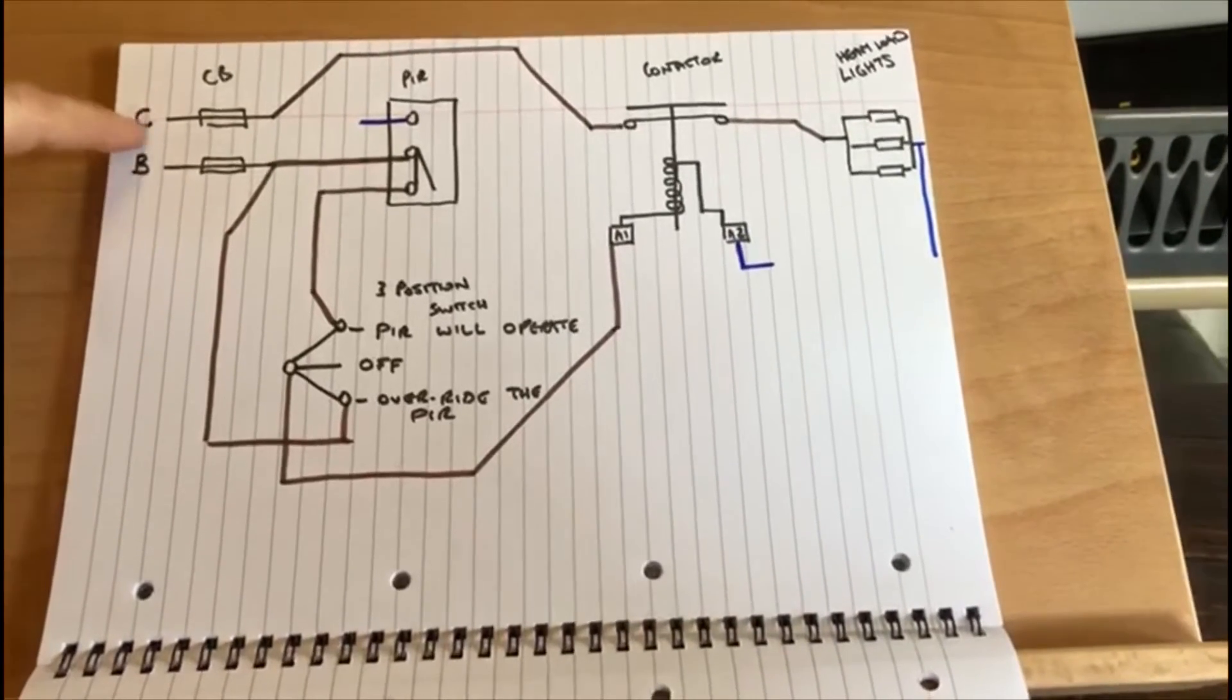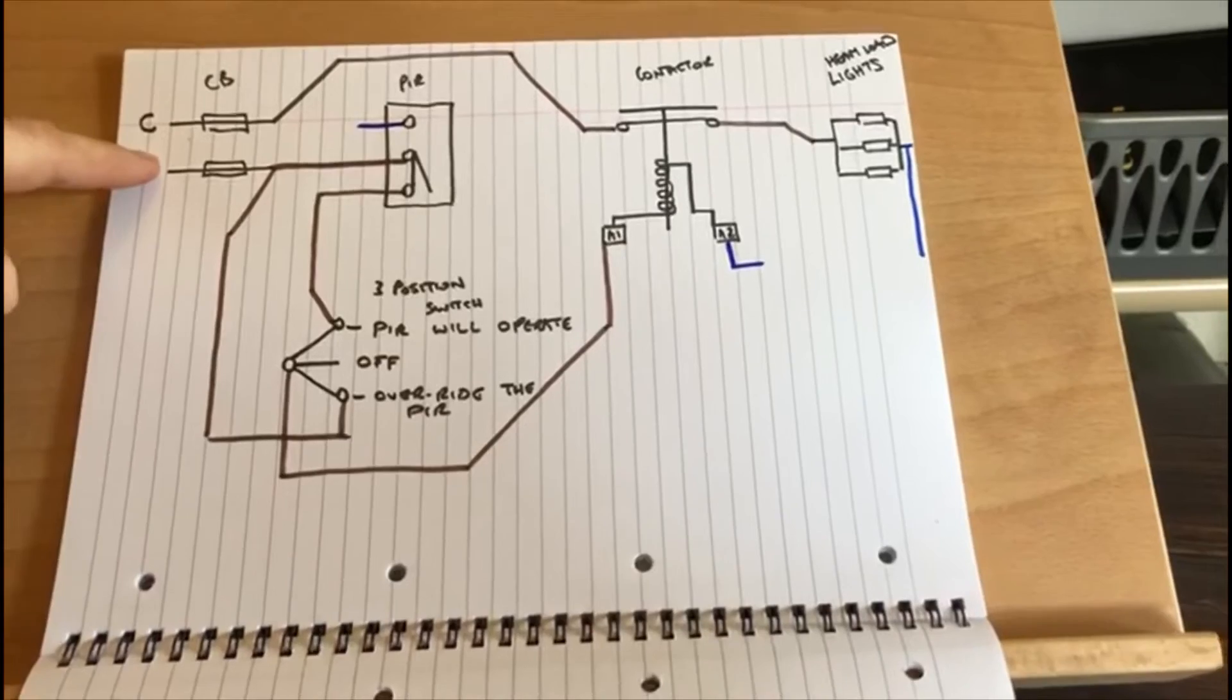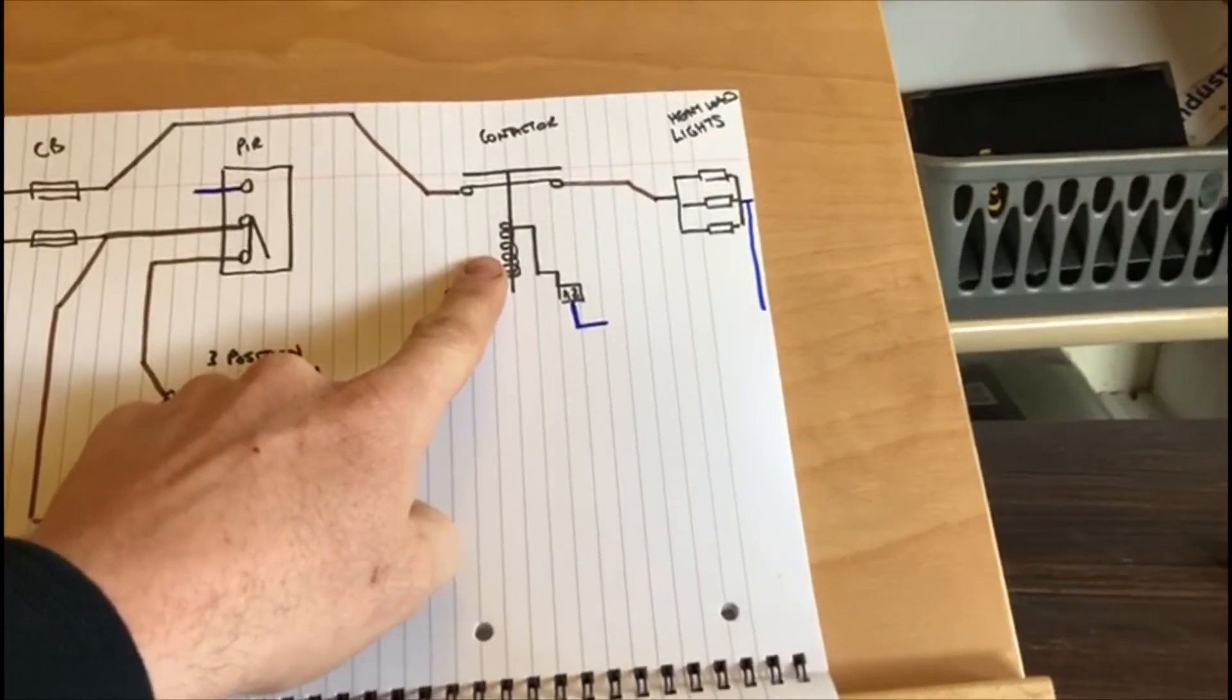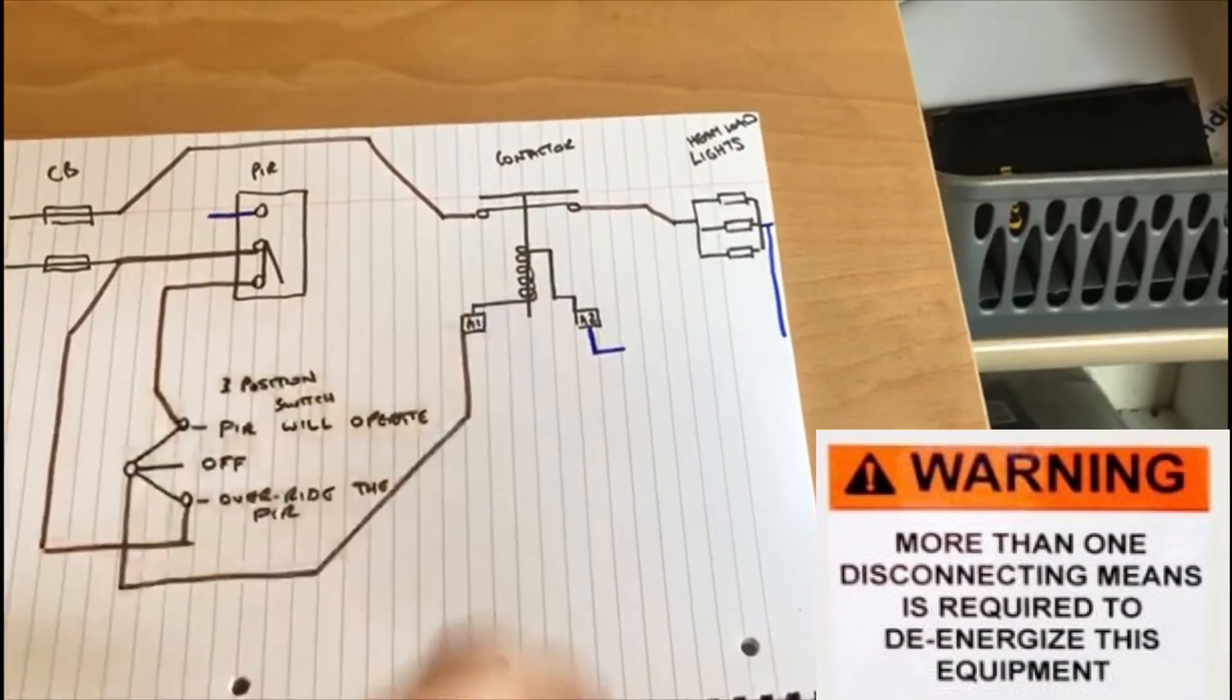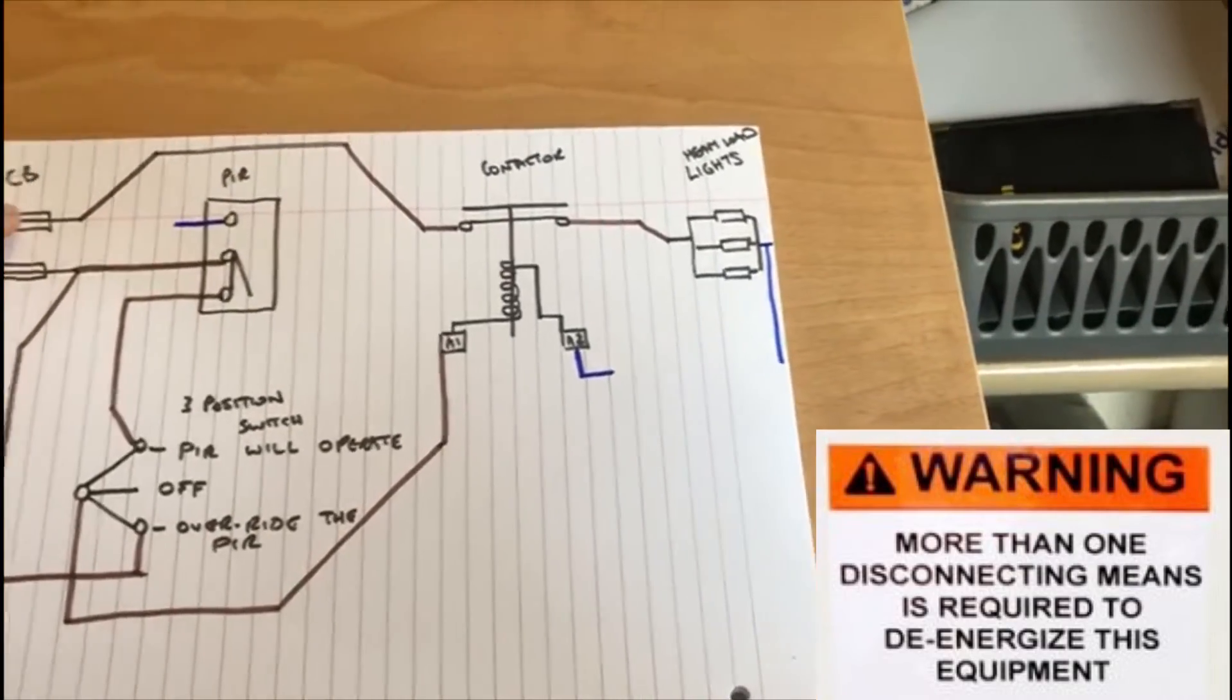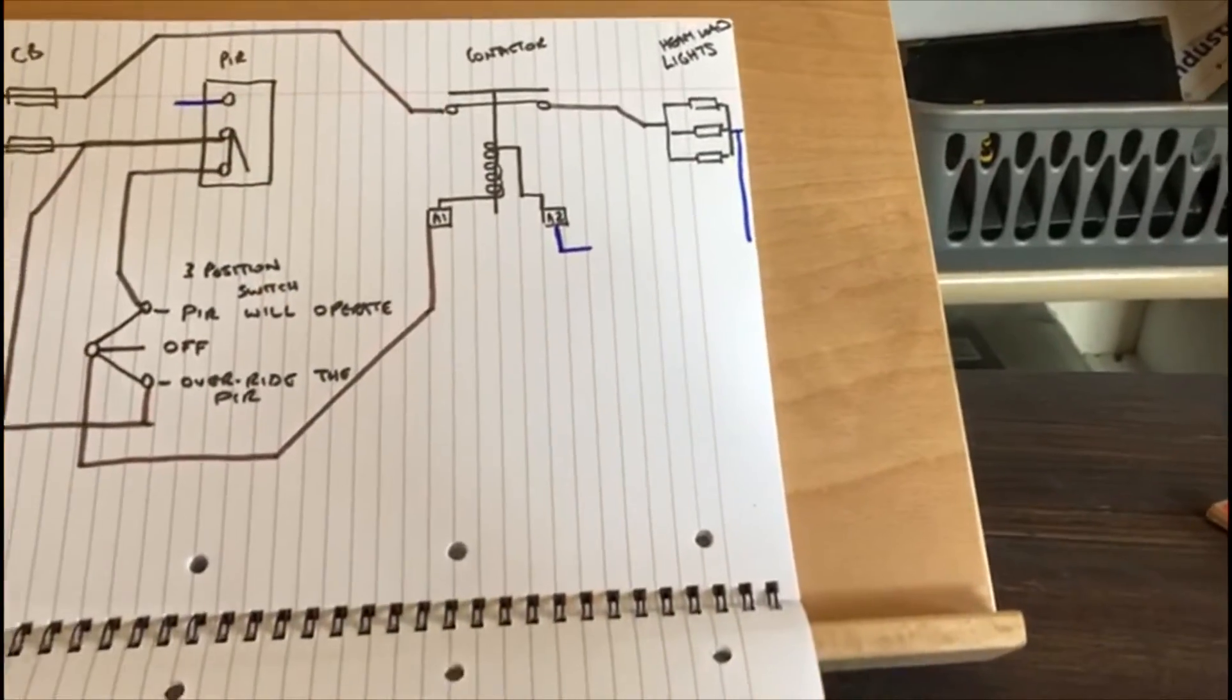Again the contactor, if we're working on the contactor, that's where the contactor needs to be labeled to say that there's two circuits going to the contactor because there's the main circuit from the C type breaker going to it and there's also the circuit going through the mid position switch, the three position switch through the B type circuit breaker.